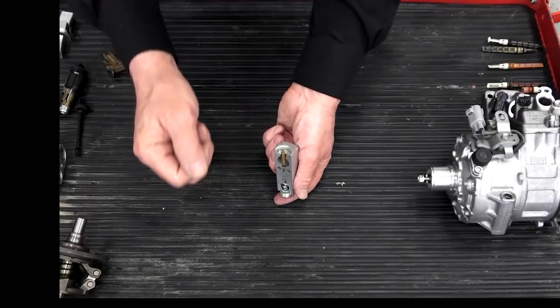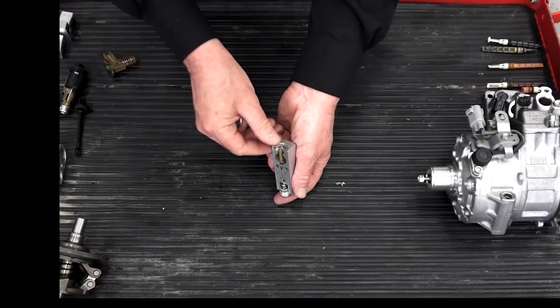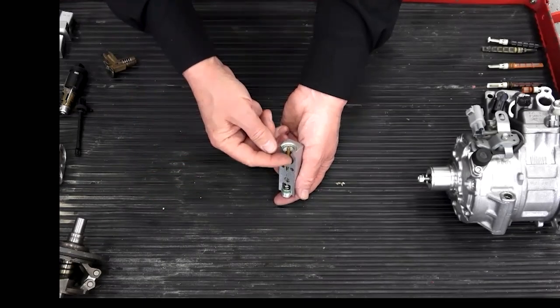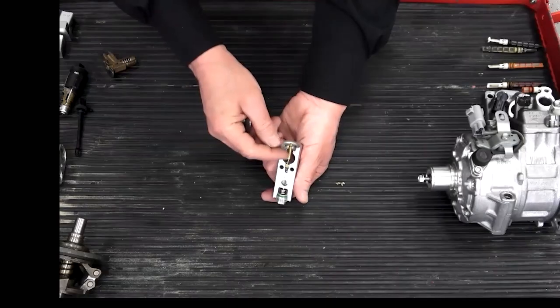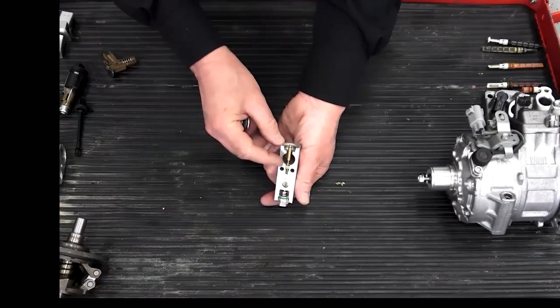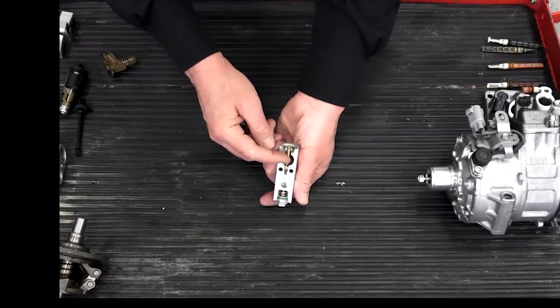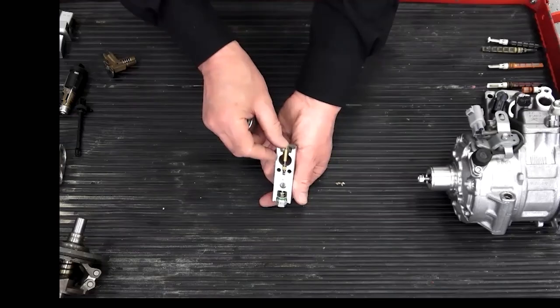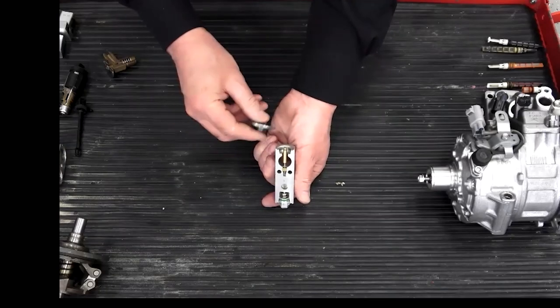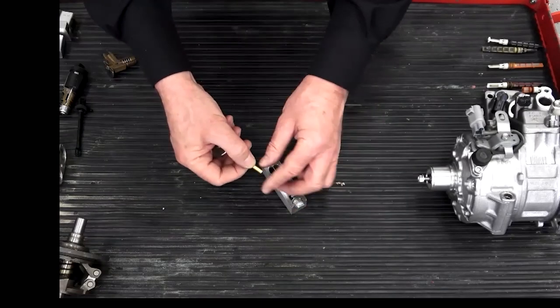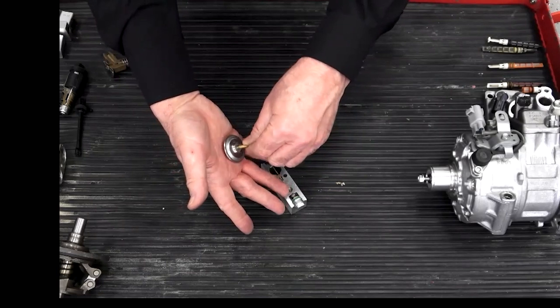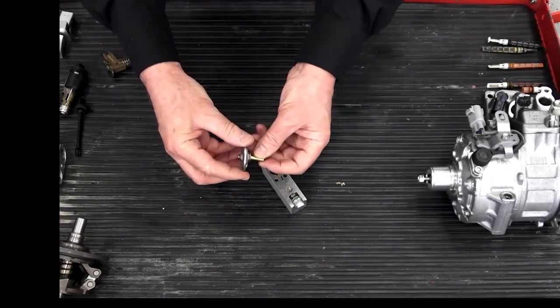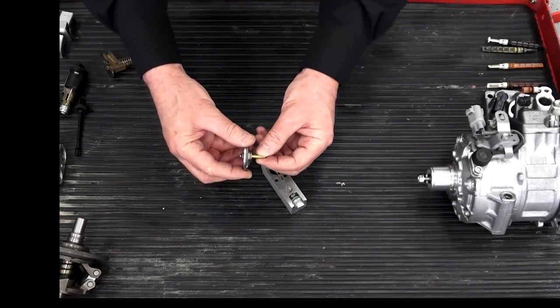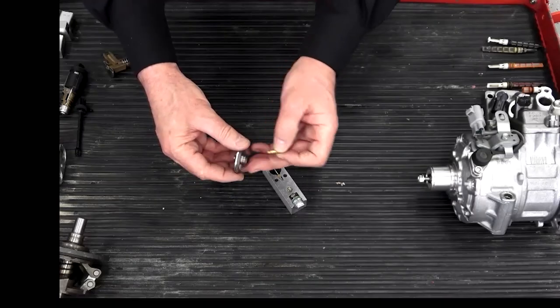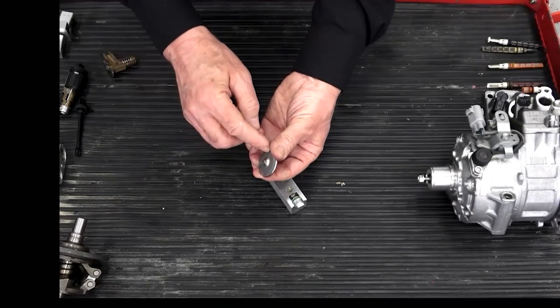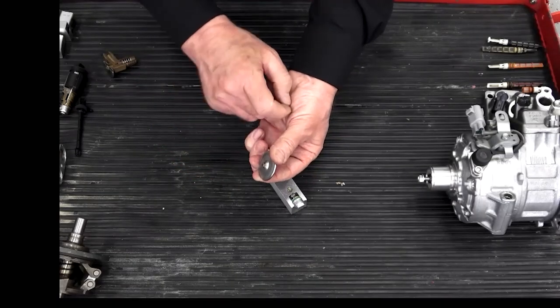So if I turn the blower from low speed to high speed, the gas coming out of the evaporator is going to get a little bit warmer. If I warm that brass ferrule, that brass rod there, that brass rod is in thermal contact with the bottom of the power valve, right? So think about it. If I warm or cool that brass rod, it's attached at the bottom of that metal diaphragm. That's going to heat or cool the refrigerant that's trapped above the diaphragm.